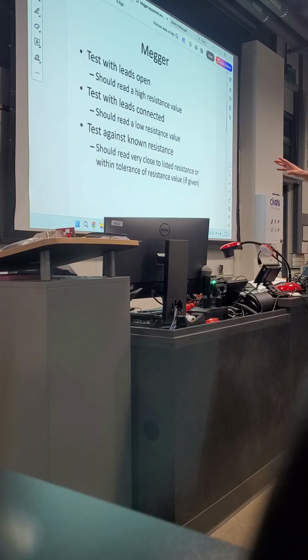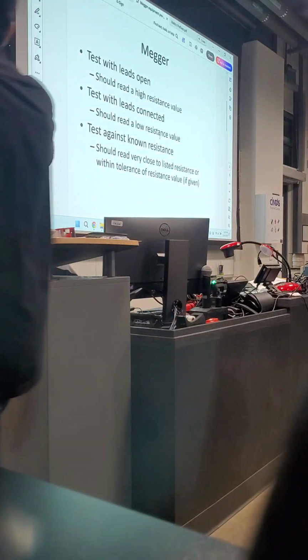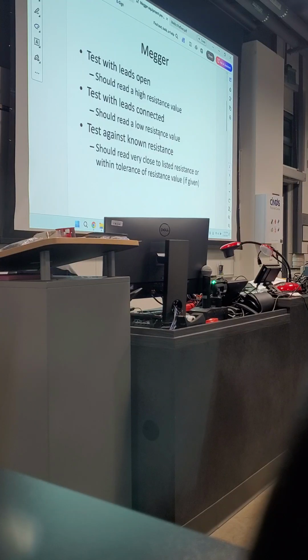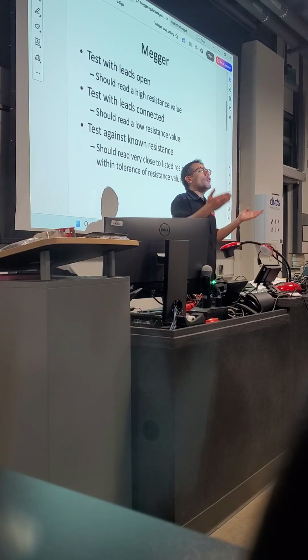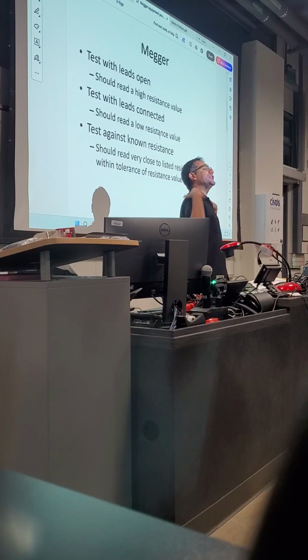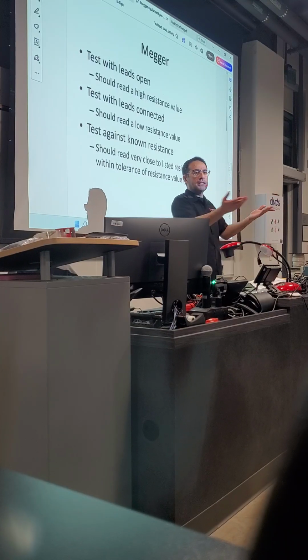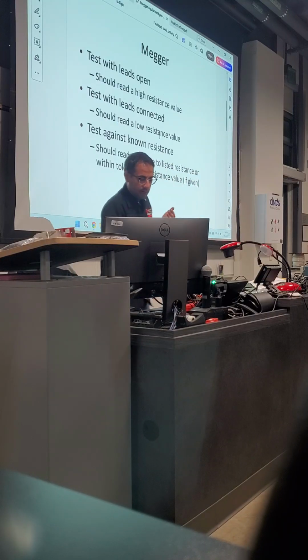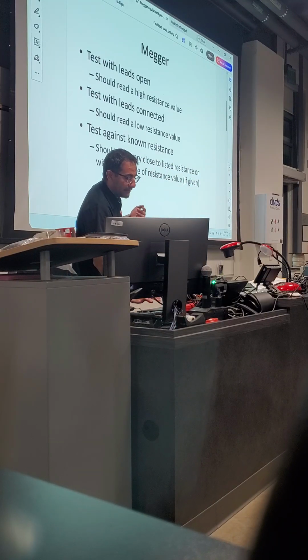We talked about the Ohm's law. We said we want to measure the resistive value, the voltage. I don't know what's the voltage. You have to look it up from table 100.1. You tell the machine how much voltage to apply. Internally, it measures the current, and then the ratio is going to be the resistance on the screen. But how long am I supposed to run the test? 1 minute. How do you know that? 60 seconds, 1 minute. It's mentioned in NETA MTS.